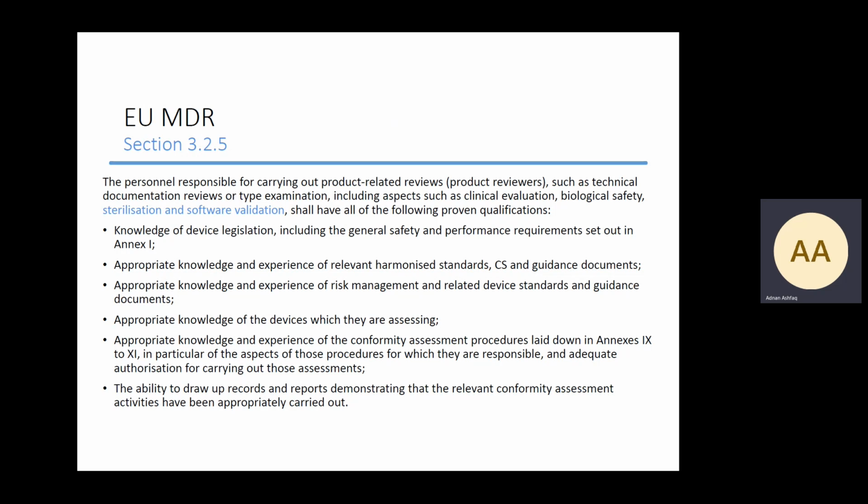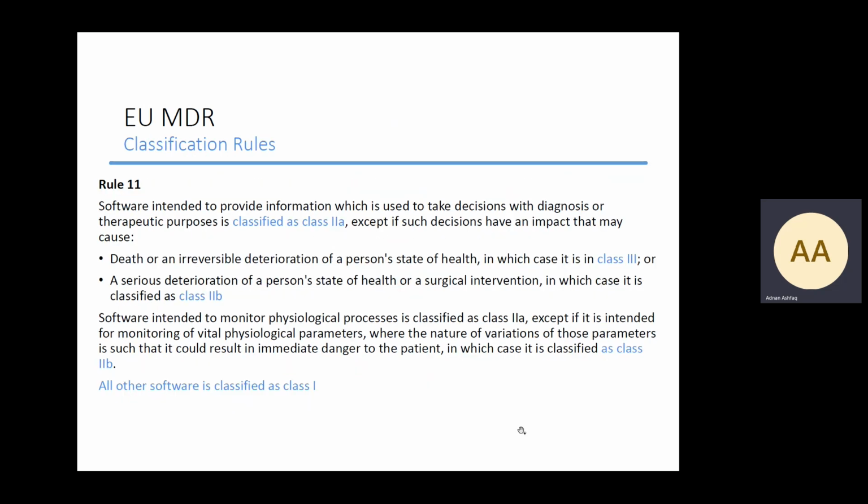Section 3.2.5 of the MDR then looks at personnel responsible, such as technical documentation reviews or type examination, including clinical evaluation, biological safety, sterilization, and software validation, who shall have the following proven qualifications. So there is an imposition of qualifications and experience that one should have in implementing such reviews of software validation. And it's also a very important point.